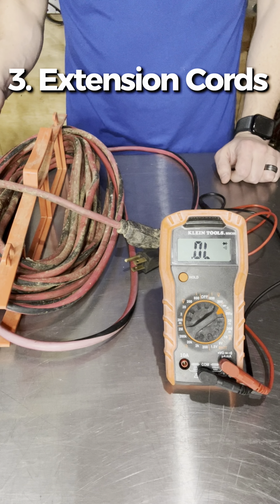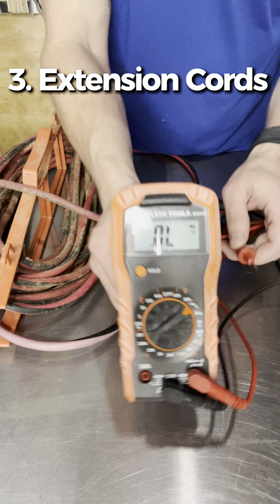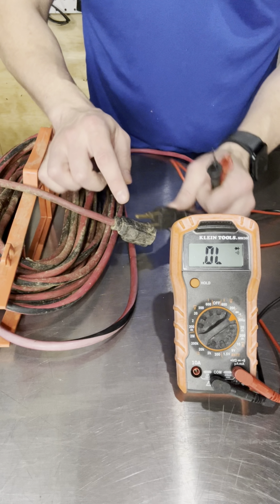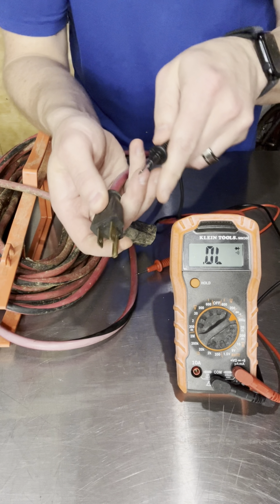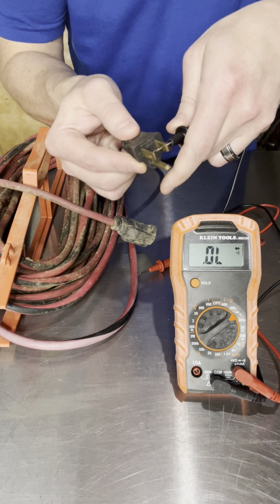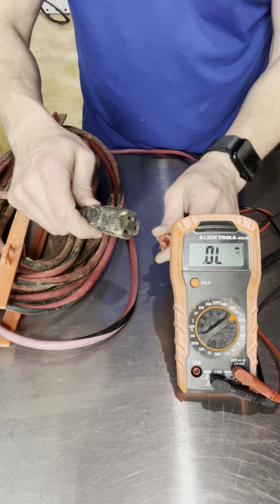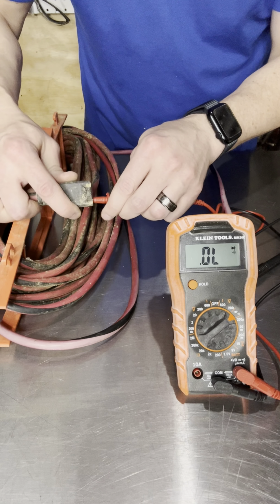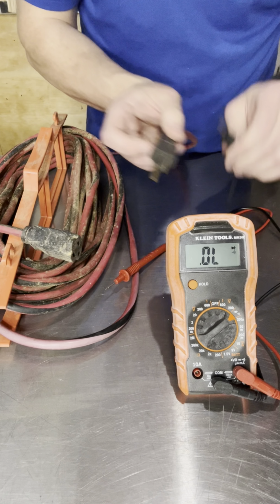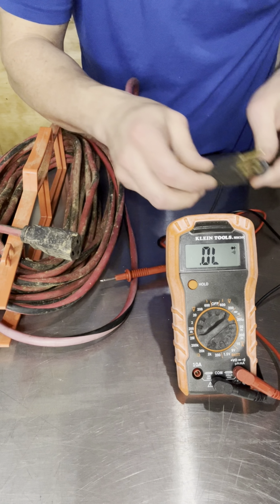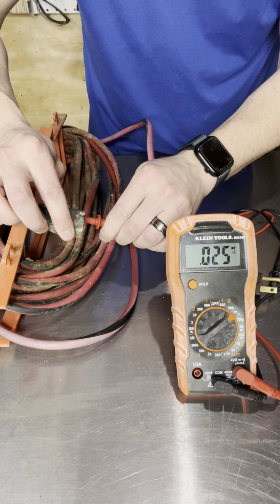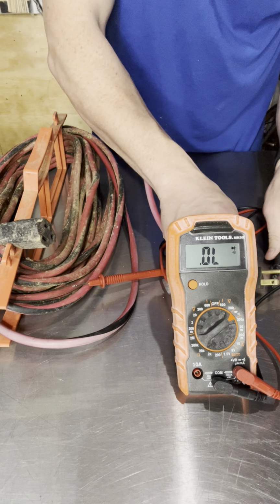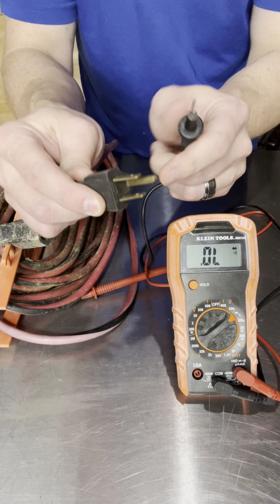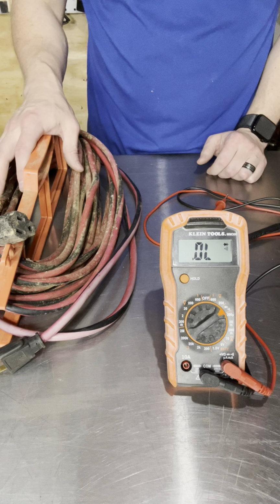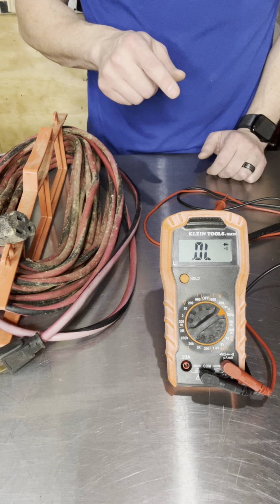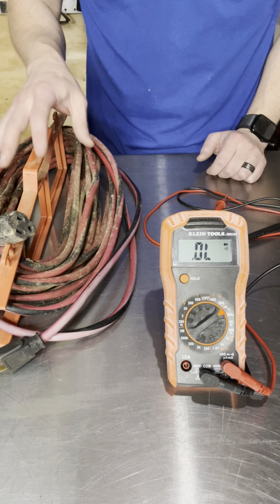Tip number 3 is the extension cord safety check. This will also use the continuity setting on your multimeter. I'm going to test each prong. I'll touch my probe to the first prong and then find the corresponding slot on the other end. That one's good. I'll change prongs and test the other slot. That's good. Then I'm going to test the ground. If your extension cord only works when you wiggle it, it's dangerous. Use the beep test from end to end on each prong. If you get no beep, then you've got a hidden break and you should stop using this cord.